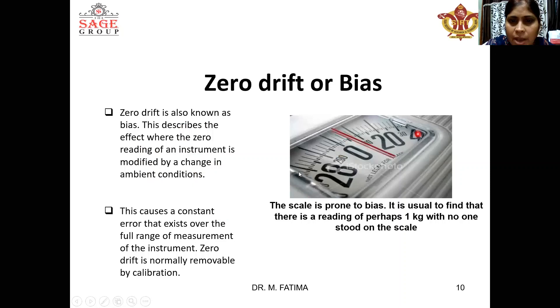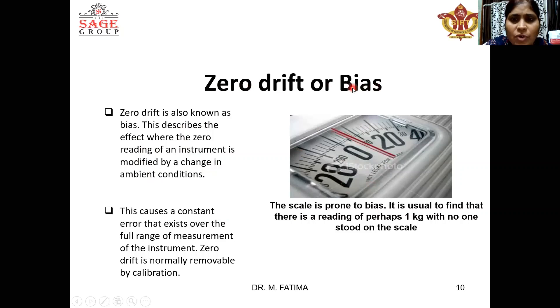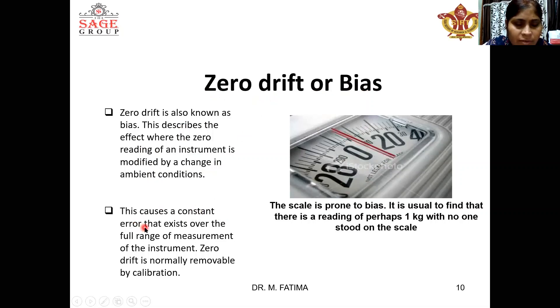Take one example. This scale is prone to bias — it is usual to find that there is a reading of approximately 1 kg or sometimes 2 kg with no one stood on the scale. So if input is not given but output is present, this is called zero drift or bias. This causes a constant error that exists over the full range of measurement of the instrument.